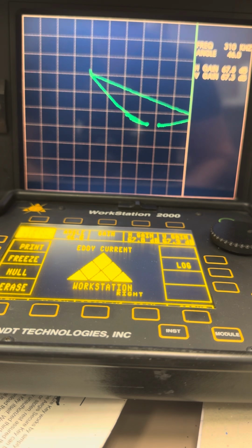You just have to account for it and know that you're not going to be as sensitive as if the material was not painted. But you can examine that as long as the paint's not more than like a quarter inch thick. That would be way, way too much for eddy current. As you know, eddy current testing is only good to around 0.2 inch, give or take. A lot of that depends on the diameter of your coil, the test frequency that you're running, and of course the material that you're testing. Wide coils have much more depth of penetration, as do low frequencies. But when you get down into the very small diameter coils and high test frequencies that they're usually operated at, you're only inspecting the very top thin layer of the material.